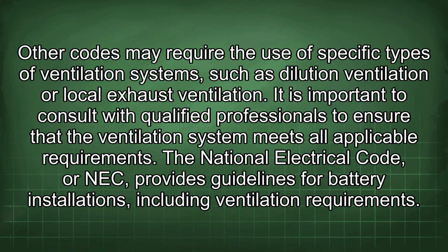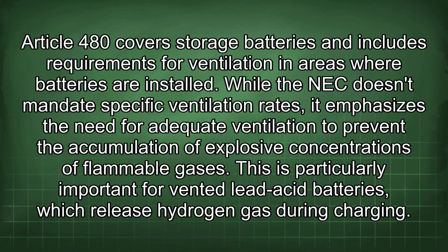The National Electrical Code, or NEC, provides guidelines for battery installations, including ventilation requirements. Article 480 covers storage batteries and includes requirements for ventilation in areas where batteries are installed. While the NEC doesn't mandate specific ventilation rates, it emphasizes the need for adequate ventilation to prevent the accumulation of explosive concentrations of flammable gases. This is particularly important for vented lead-acid batteries, which release hydrogen gas during charging.